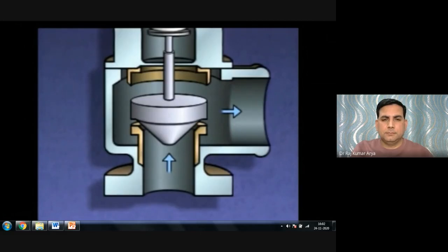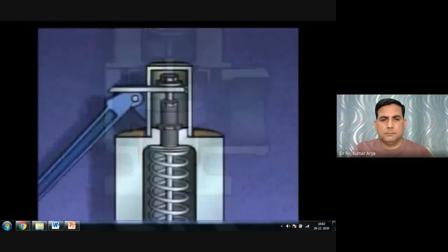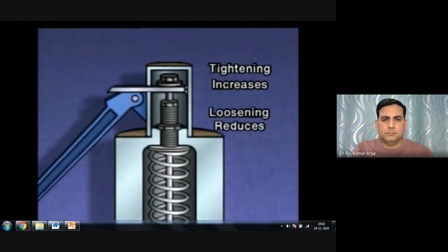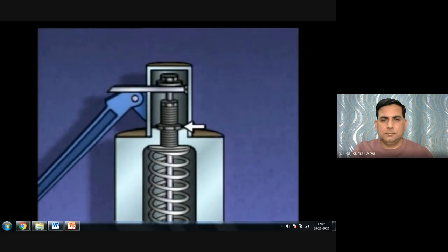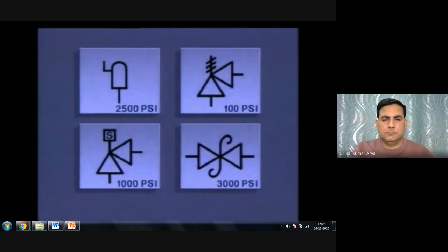The opening pressure setting can be changed using the adjusting screw. Tightening the screw increases the force on the disc, raising the pressure setting; loosening it allows the valve to open at a lower pressure. The lock nut holds the adjusting screw in position. On a piping system diagram, a safety valve can be represented by various symbols, similar to those used for relief valves, and the valve's operating set point is often included beside the symbol.